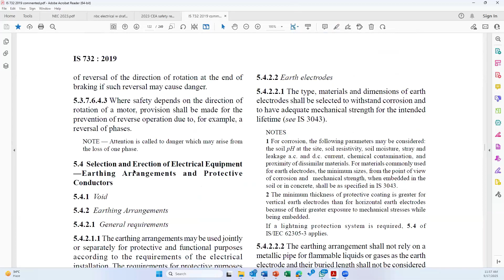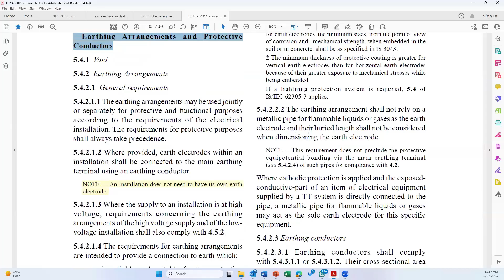You can see here, 5.4 talks about selection and erection of electrical equipment, earthing arrangement, protective conductors. Now there is a note. You can see this note very clearly: an installation does not need to have its own earth electrode. That means your industry, your house, your installation, your building doesn't need to have its own earth electrode, which is applicable for electrical installation up to 1000 volt AC, 1500 volt DC.